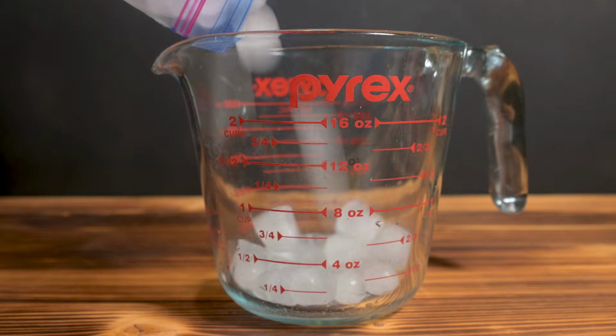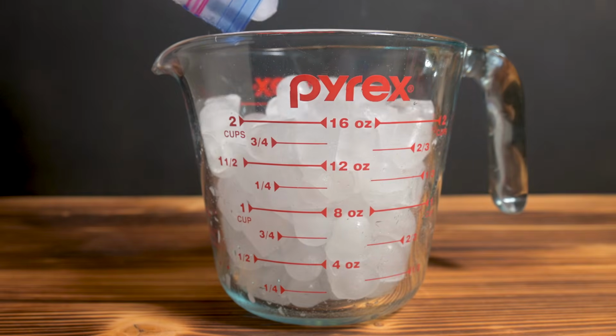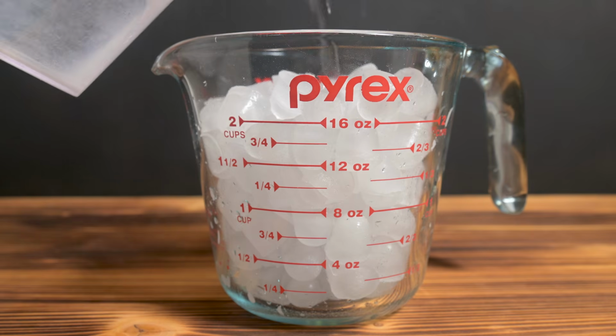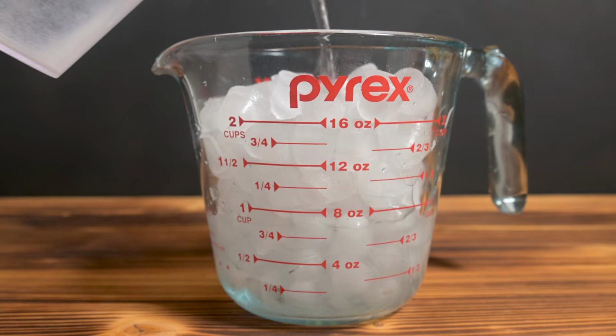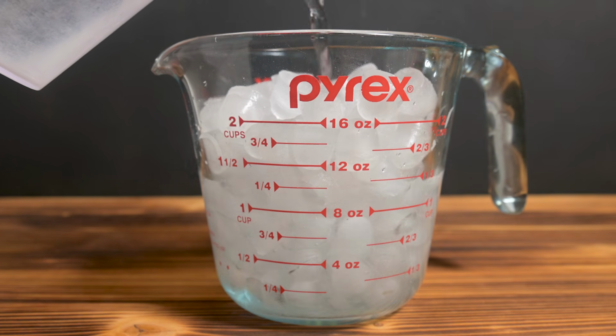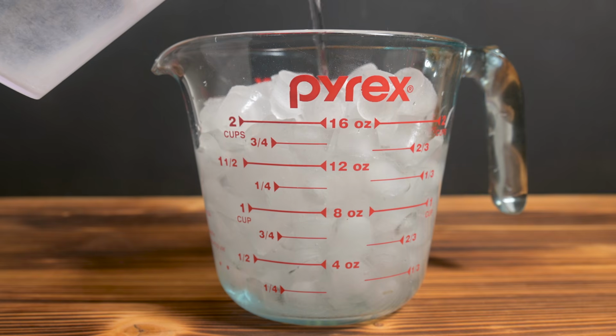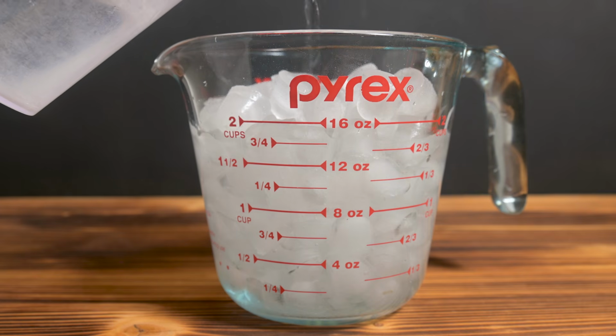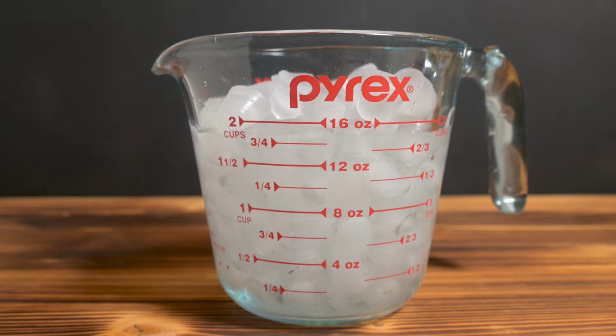And the first method for checking your thermometer is the ice bath method. To do that, you're going to fill a container with crushed ice, then add water up to about half an inch below the top of the ice. That helps ensure that the water is 32 degrees Fahrenheit. Now, if you add too much water, that ice is going to start to float and you're going to have a big dead spot at the bottom, and that water won't be at 32. It'll mess up the entire test. So it's really important that you do it this way.